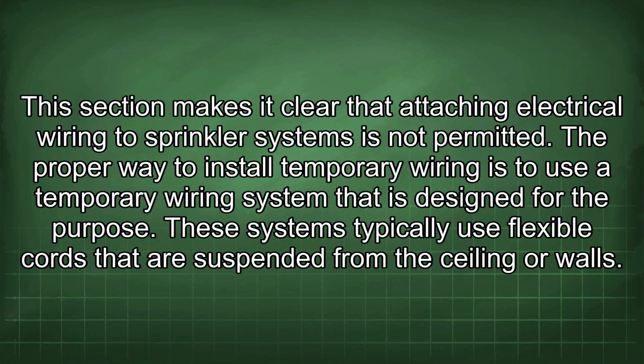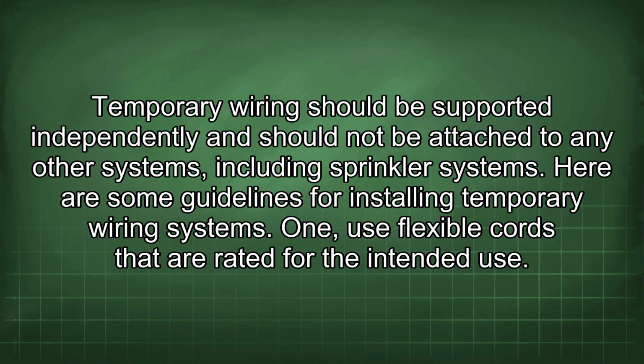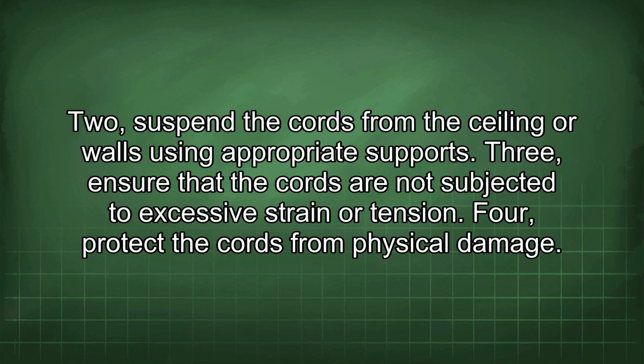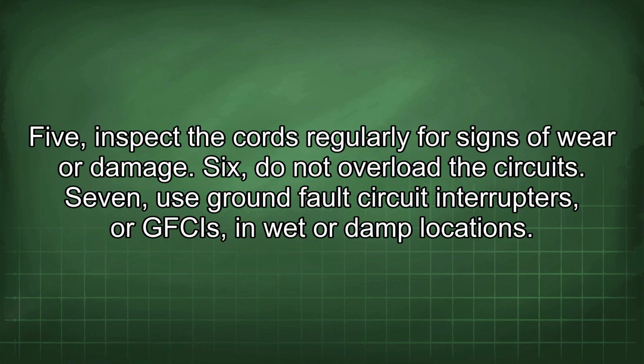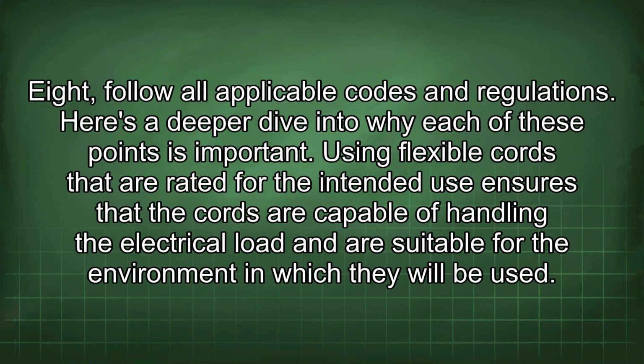The proper way to install temporary wiring is to use a temporary wiring system that is designed for the purpose. These systems typically use flexible cords that are suspended from the ceiling or walls. Temporary wiring should be supported independently and should not be attached to any other systems, including sprinkler systems. Here are some guidelines for installing temporary wiring systems. 1. Use flexible cords that are rated for the intended use. 2. Suspend the cords from the ceiling or walls using appropriate support. 3. Ensure that the cords are not subjected to excessive strain or tension. 4. Protect the cords from physical damage. 5. Inspect the cords regularly for signs of wear or damage. 6. Do not overload the circuits. 7. Use ground fault circuit interrupters, or GFCIs, in wet or damp locations. 8. Follow all applicable codes and regulations.